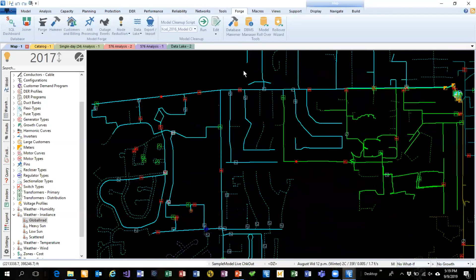As far as amps go, my current flow is going to be the same. The difference is in the way we tally up the losses. Because if I have 50 kW on this section and it's all primary analysis, it's 50 kW of load. But if I take that 50 kW and spread it down to the customers, now I've got the transformer losses.